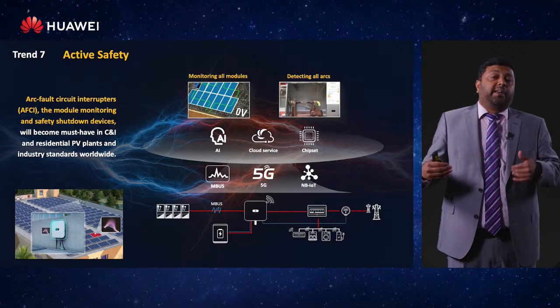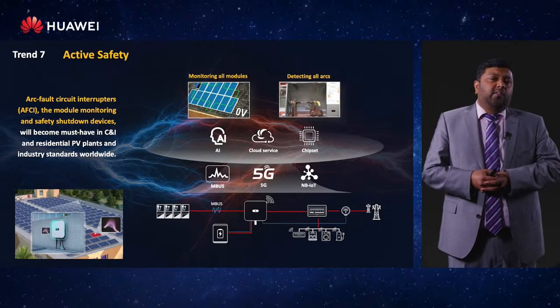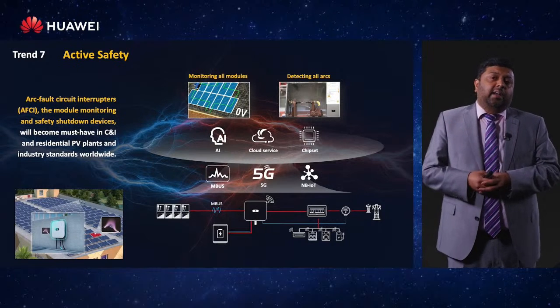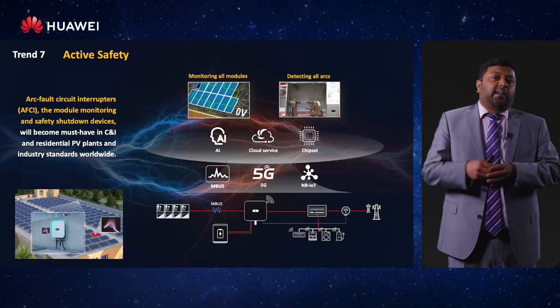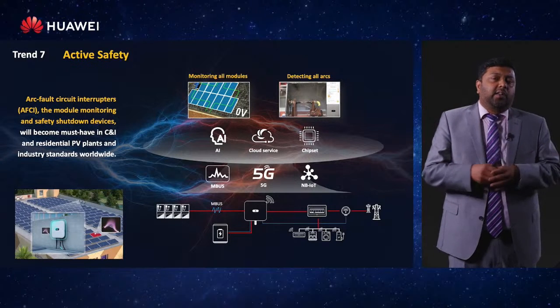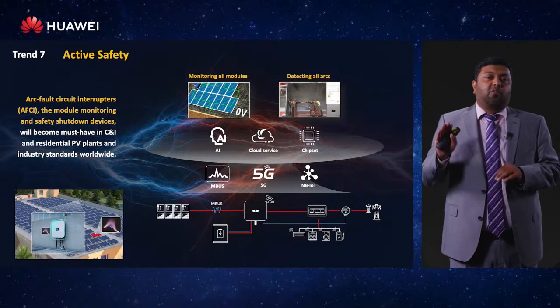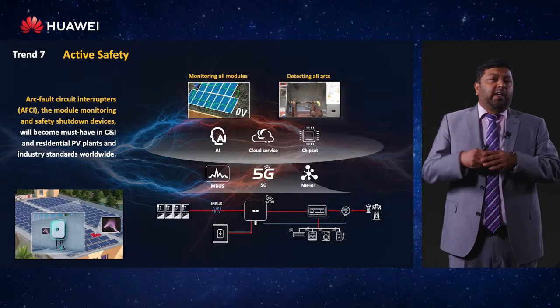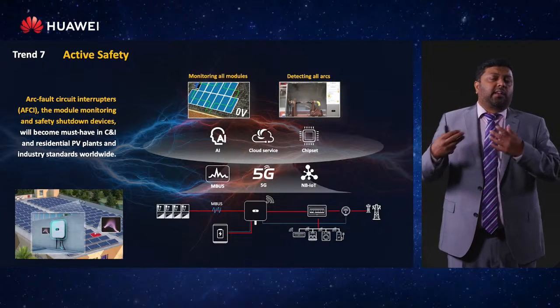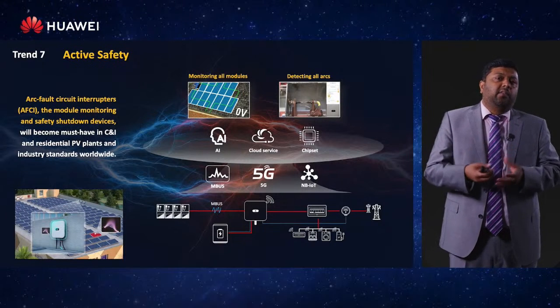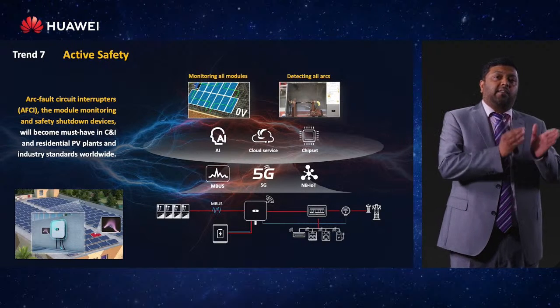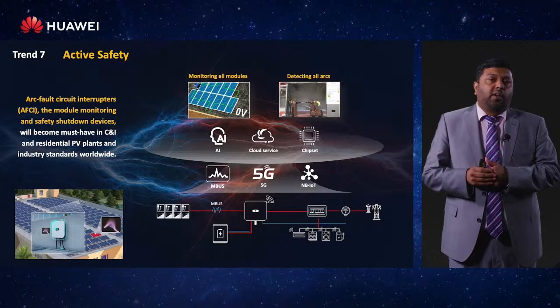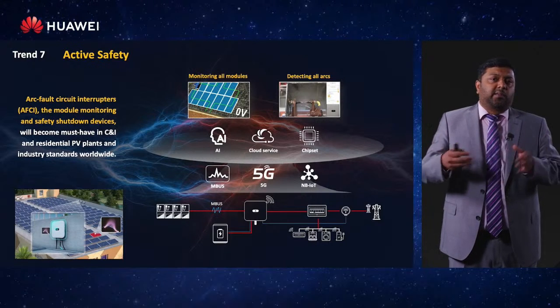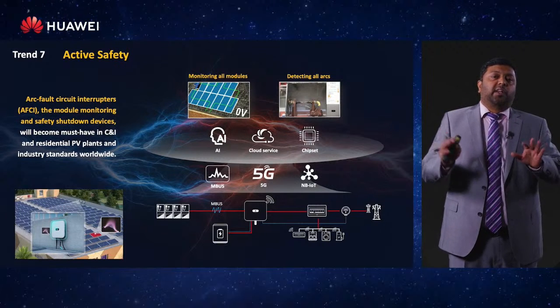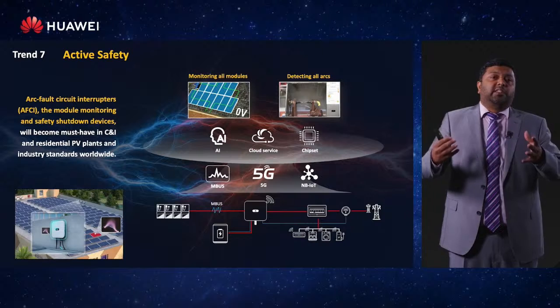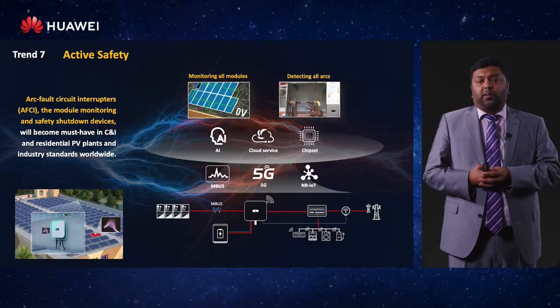These arcs are quite dangerous because they can create a fire. There needs to be a system that detects an arc, but doesn't mistake noise for an arc, distinguishing real arcs from false positives. This is done through an intelligent algorithm, using deep learning to determine if an arc has really happened or if it's just noise from other power converters and systems. Making this correct prediction is becoming more and more important and imperative, and that is the active safety method.